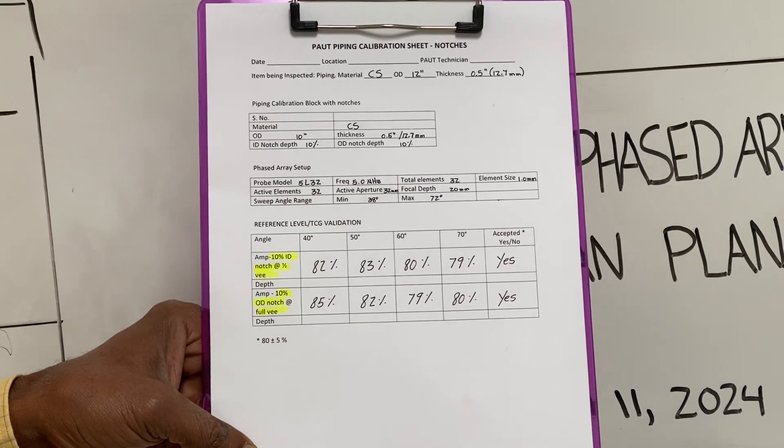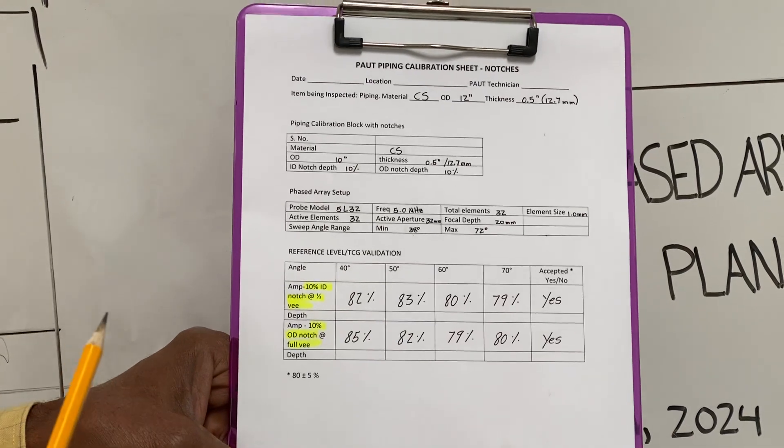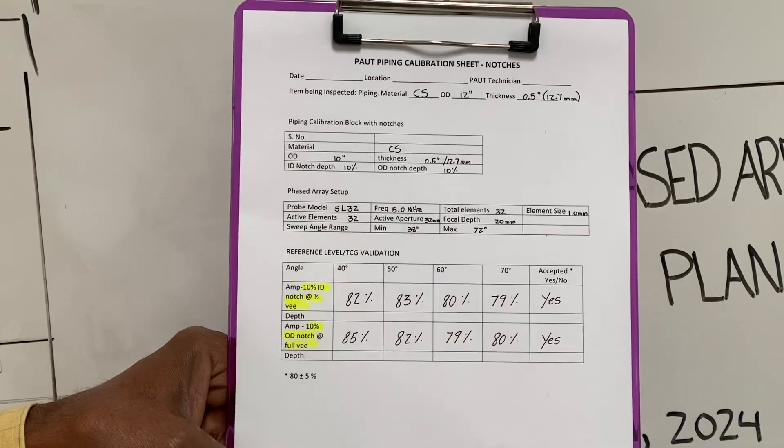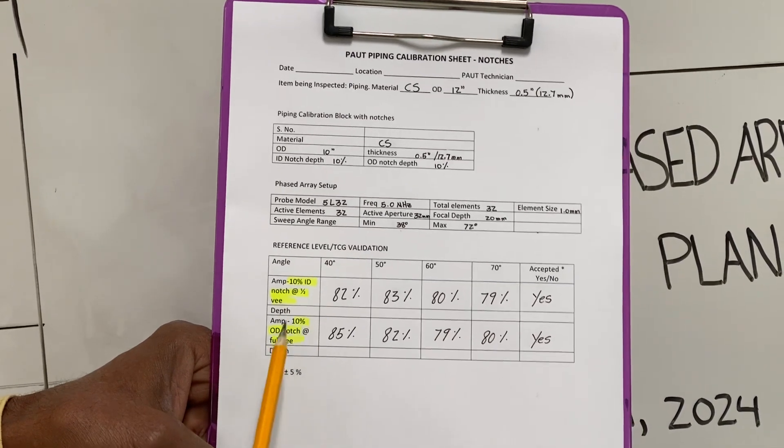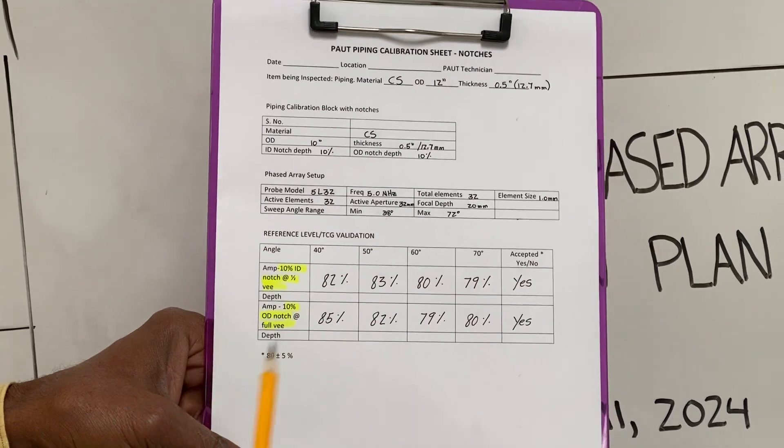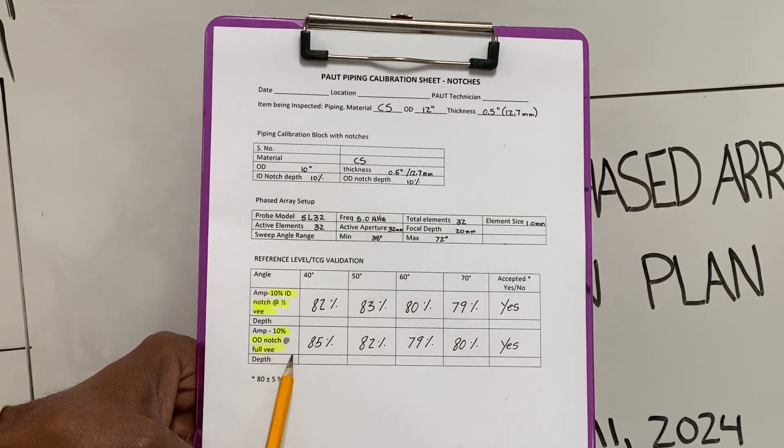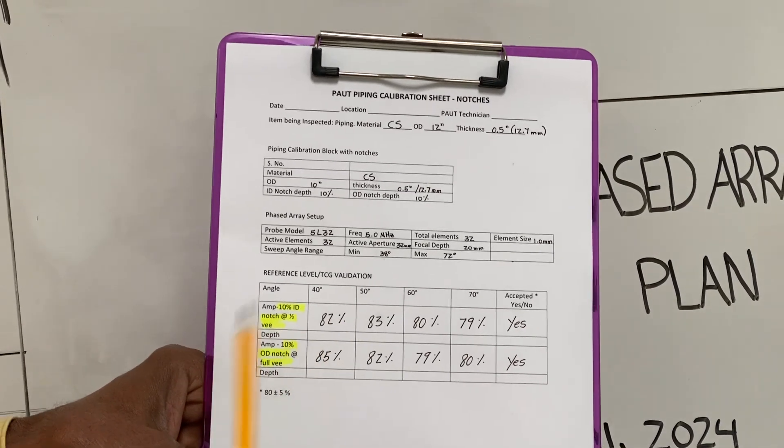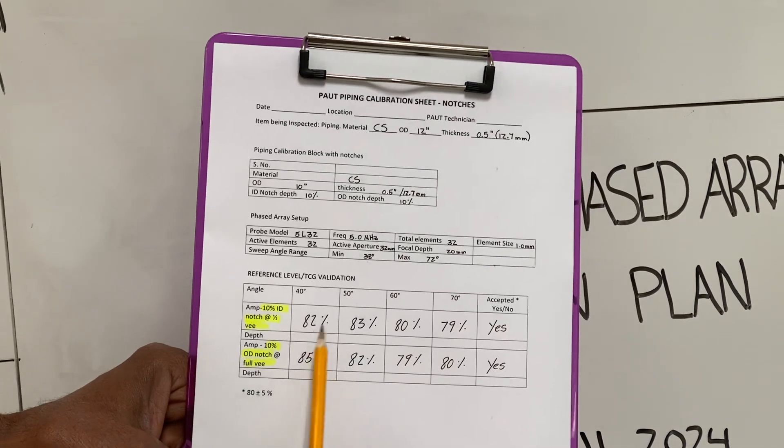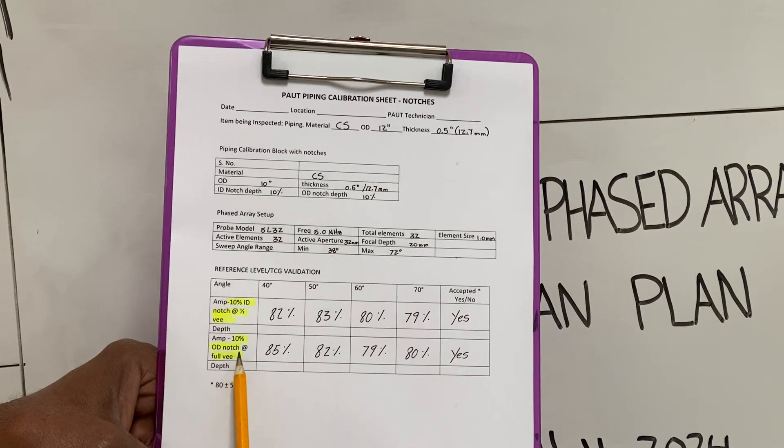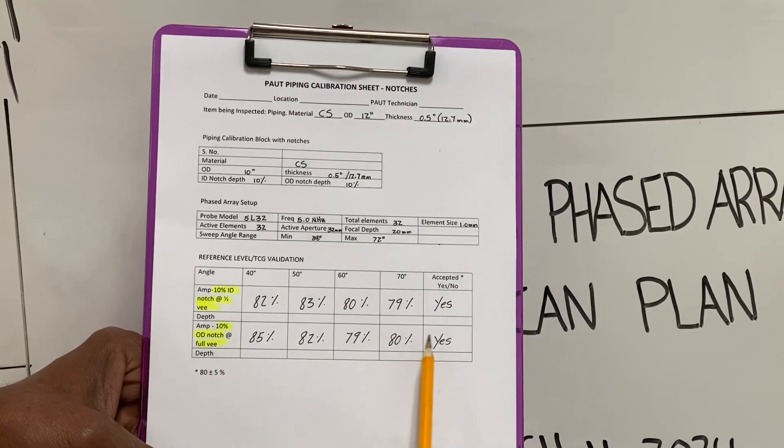In order to make sure that your calibration is valid, what needs to be done like I discussed in the last lecture of February 24th is that you have to take the measurements at 40 degrees, 50, 60, and 70 to make sure that you're getting an amplitude on the ID notches and the OD notch which is about 80%. So here we have 82, 83, 80, and 79. So this is an acceptable calibration on the OD notch, full V path, and this is also acceptable.